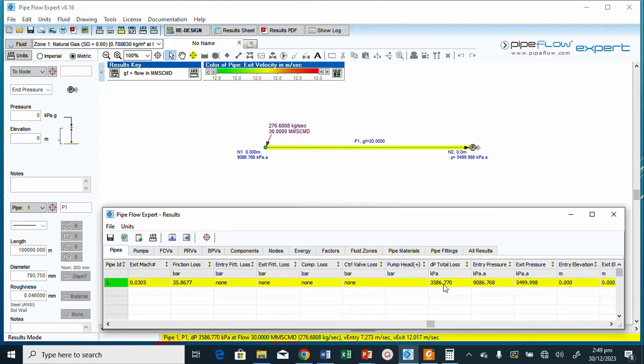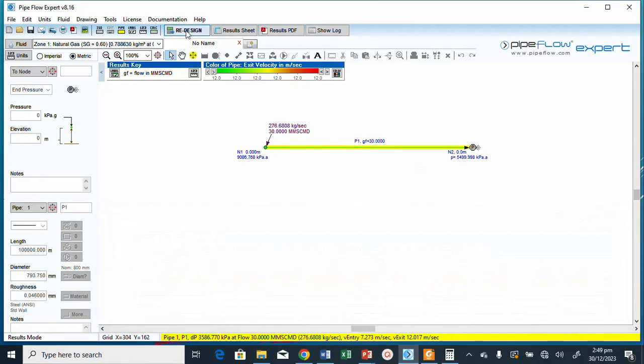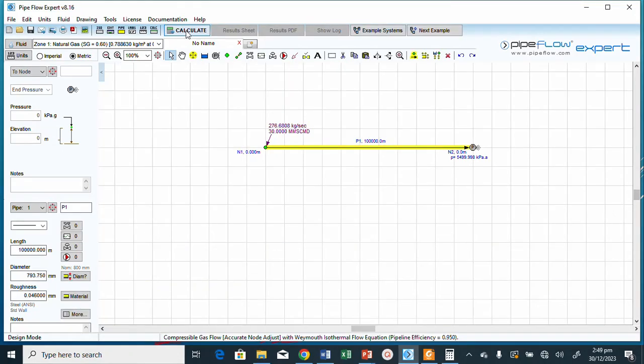With 800 mm, the entry pressure is 9086 kPa — still above 8500 kPa, though the pressure drop has reduced drastically to about 3586 kPa. We're looking for an entry pressure of 8500 kPa, so 800 mm is still not quite right. Let's try 900 mm.